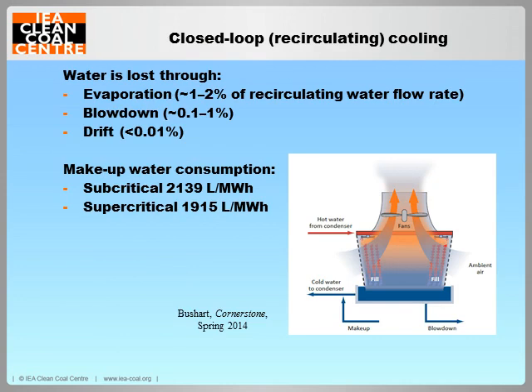The most common cooling system employed in modern power plants is a closed loop or recirculating cooling tower. The hot water from the steam condenser is pumped into a cooling tower where it is sprayed over the tower fill. As ambient air passes through the warm water, a portion of the water evaporates, cooling the remaining flow. The cooled water is collected at the bottom of the tower and is pumped back to the condenser tube inlets. This figure shows the water flow in one cooling tower design, which is in this case an induced draft cooling tower.